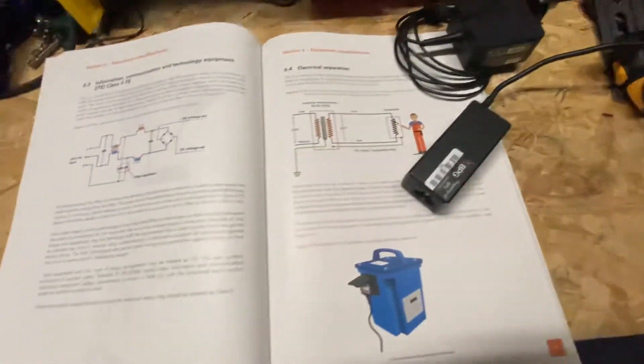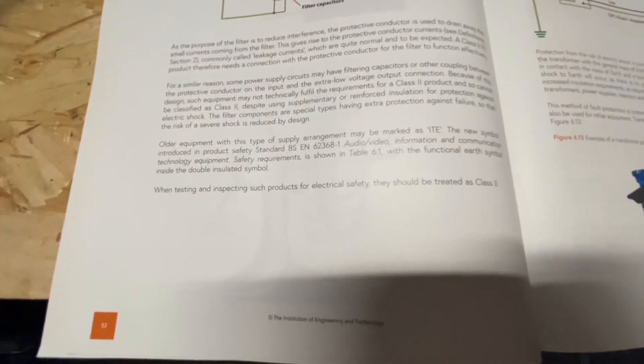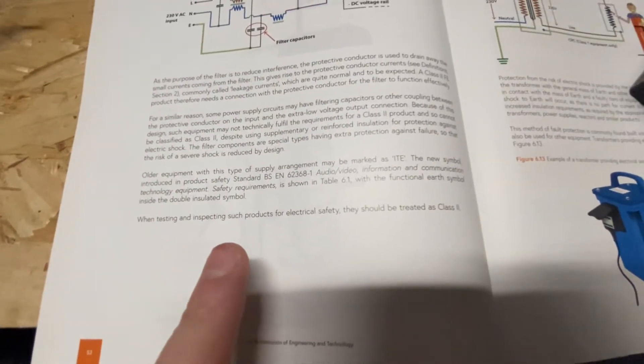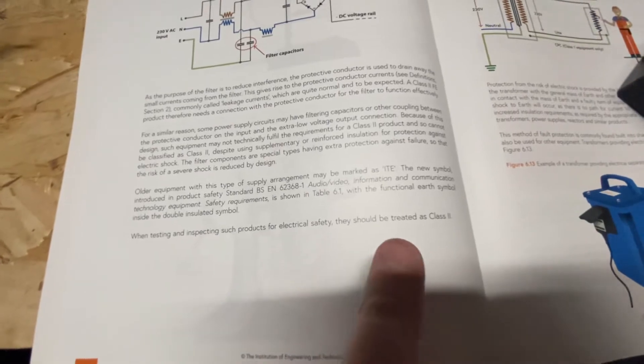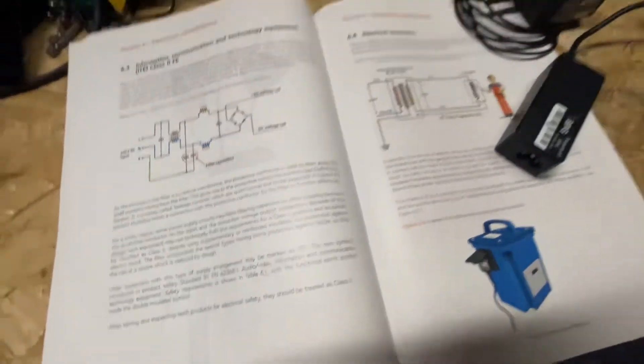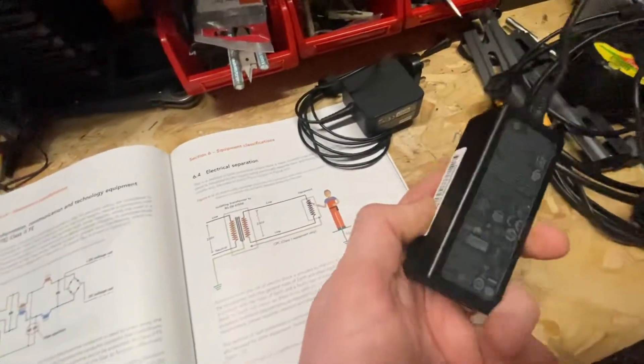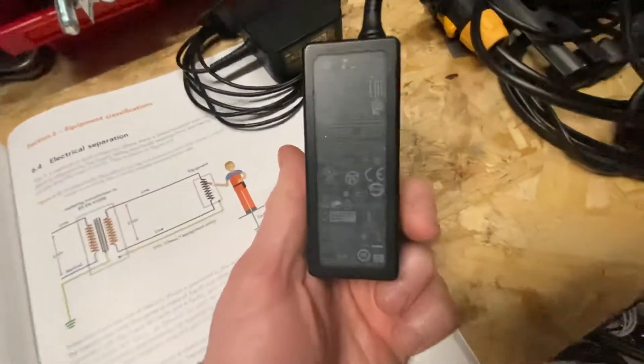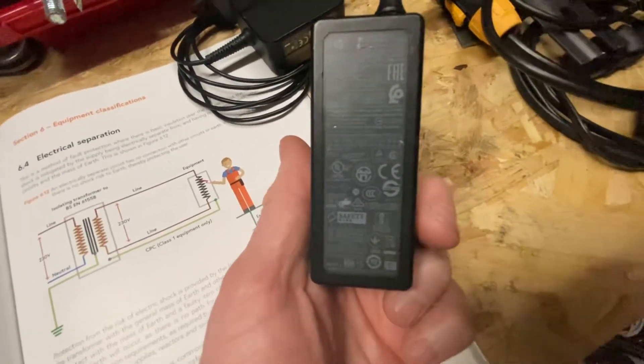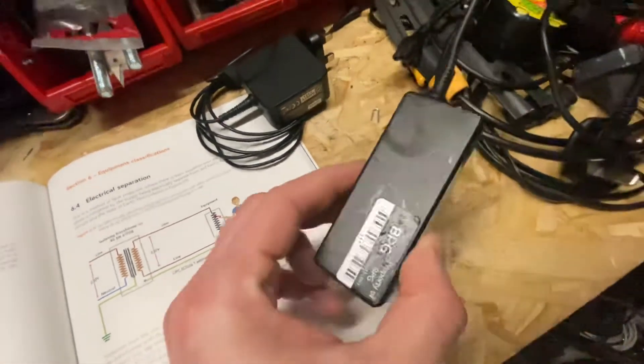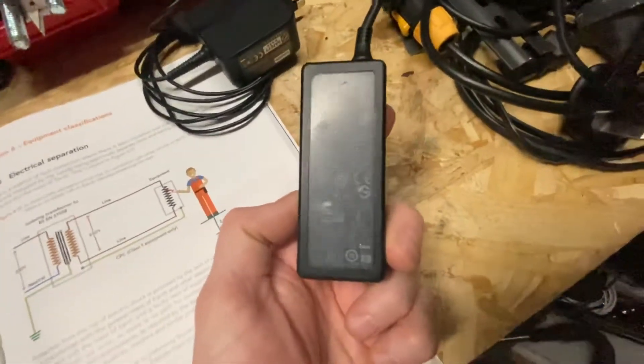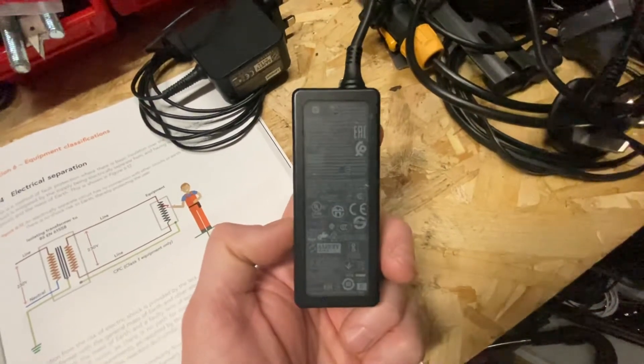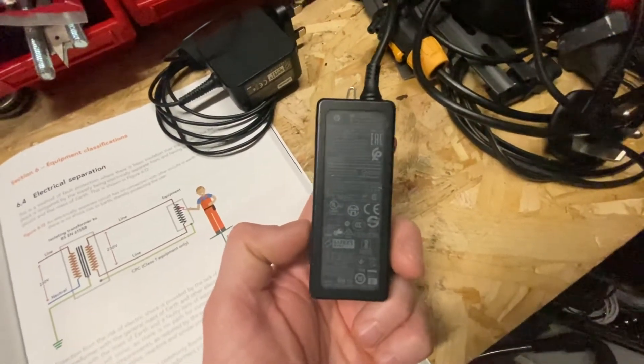Now in the code of practice, you'll see as well at the bottom there, it's quite important. When testing and inspecting such products, they should be treated as class 2. So the code of practice says they're class 2. But if you see on the back, there's no class 2 symbol, so that's where things can get a bit confusing because I was always taught if it doesn't have a class 2 symbol, you treat it as class 1.